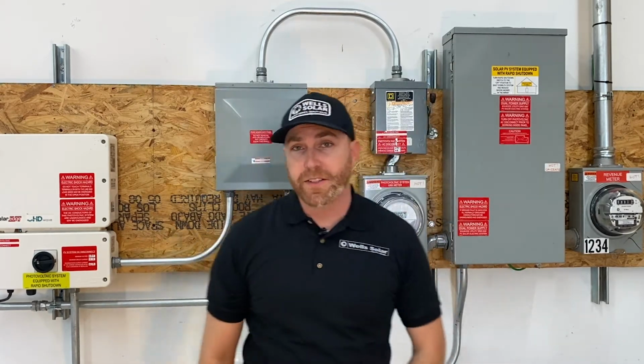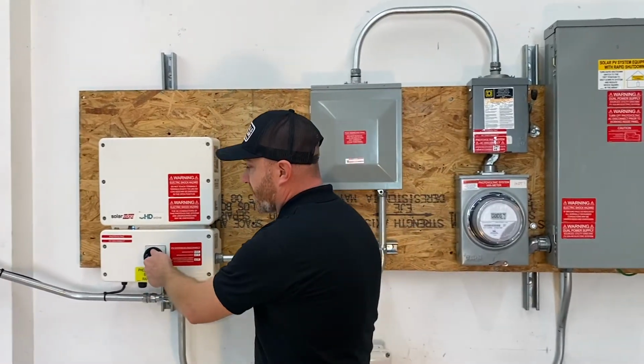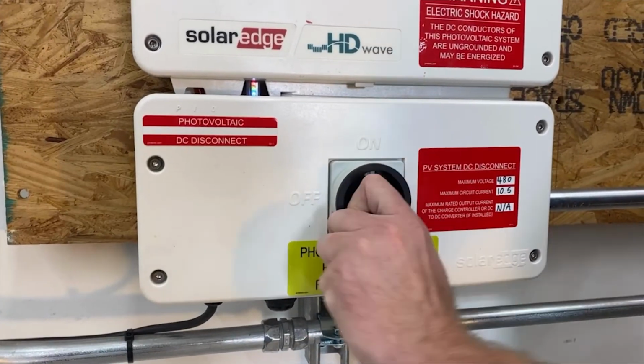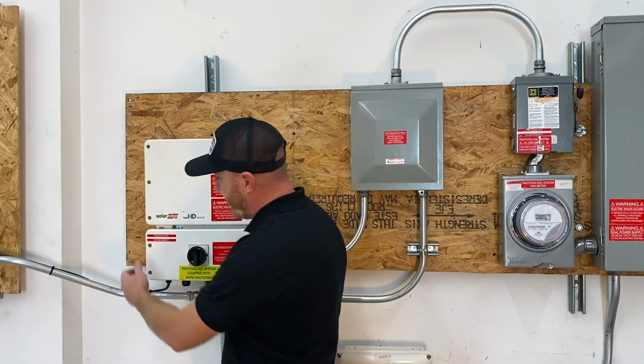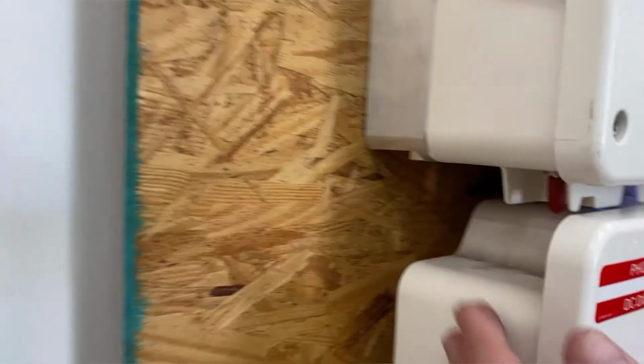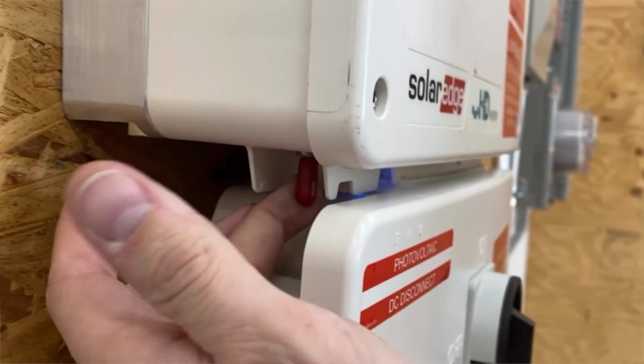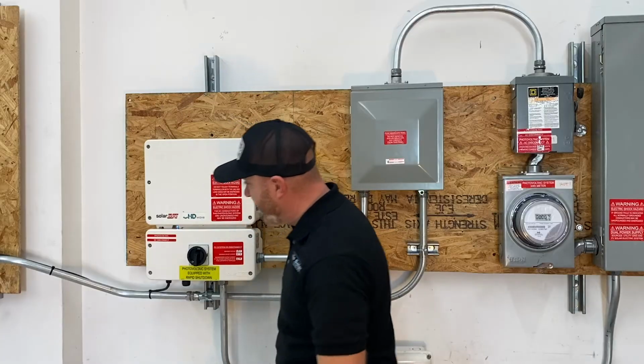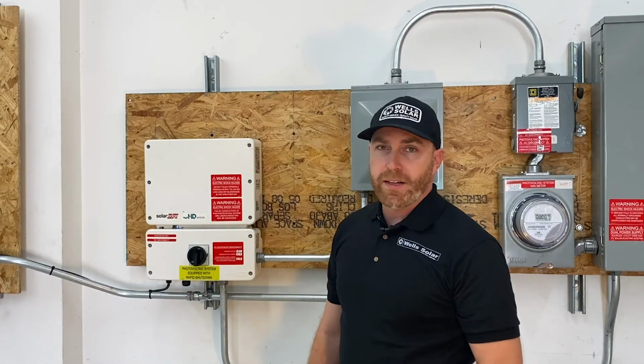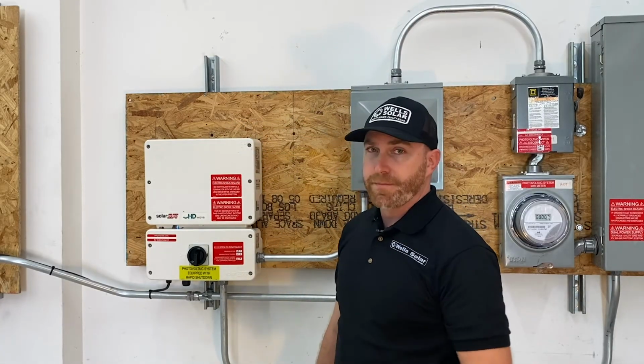Then we'll move back over to the inverter. You're going to want to turn the rotary switch back to the on position. Then on the left, we'll pull that little red switch to the left and hold it there for 2 seconds. Let it go. It'll go through a 5-minute wake-up period where it's going to monitor the grid.